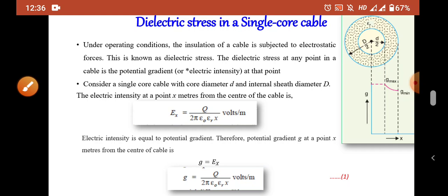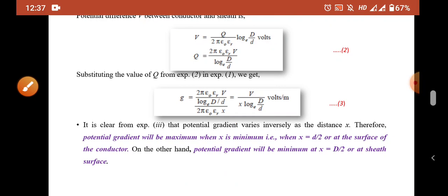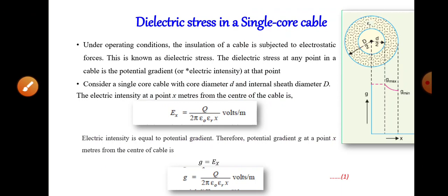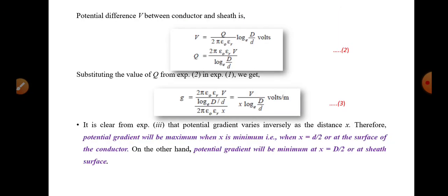In this equation we need to substitute for q. We know that the potential V between the conductor and sheath is: V = q / (2π·ε₀·εᵣ) · log_e(D/d) volts. This equation is obtained from the capacitance of a single core cable — please refer to that derivation. From this, q = 2π·ε₀·εᵣ·V / log_e(D/d). Substituting into the equation for G gives: G = V / (x · log_e(D/d)).